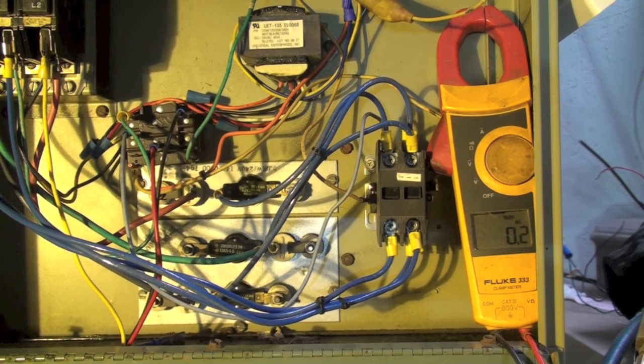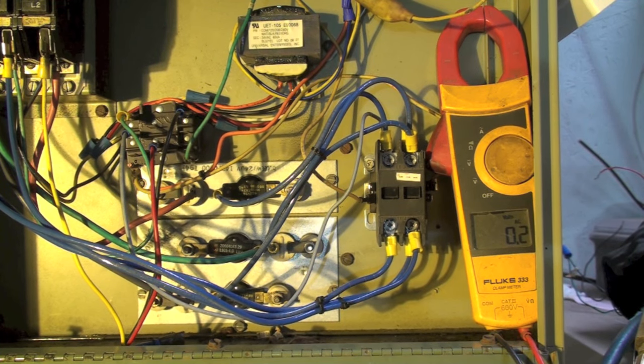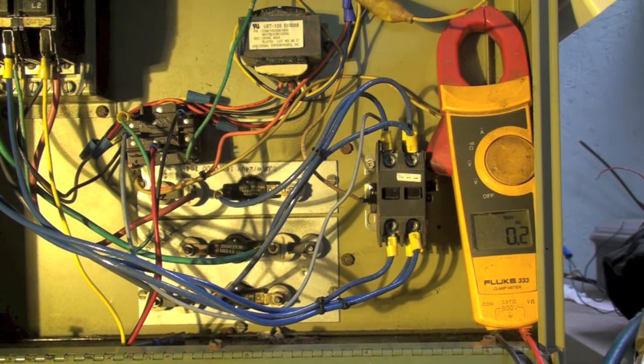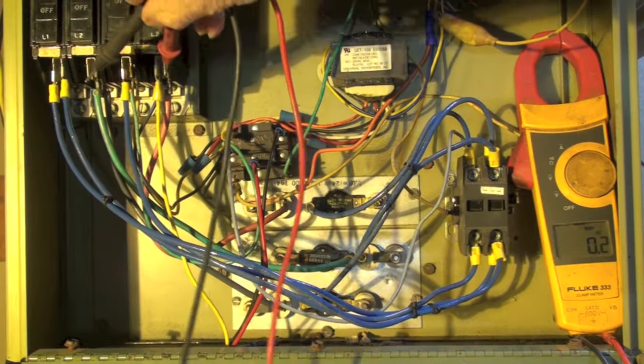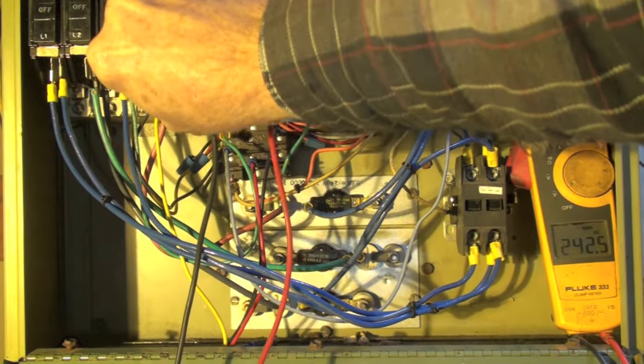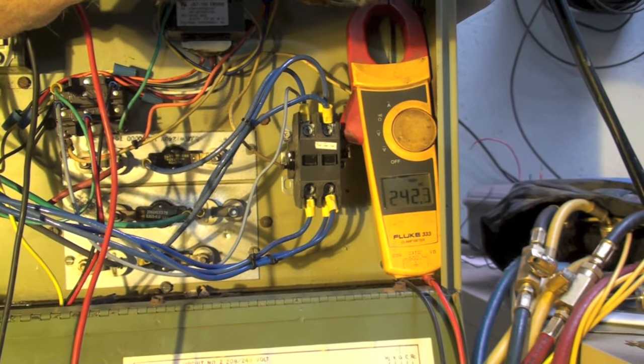Okay, the first thing I'm going to do is check to see if there's power. I'm almost certain there is because the fan's running. I'm going to check up here across this breaker. You'll notice we have 242, so we have power available.